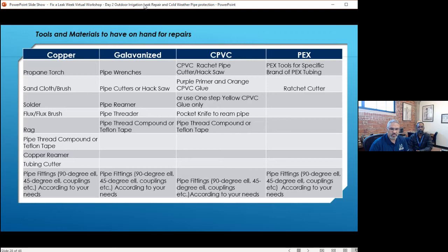You have to use specific tools for PEX installs. You would also use a ratchet cutter. Some PEX piping uses an expander tool that expands a ring to place over the fitting to make the connection and hold it in place. Others have more specific tools for that use. Again, the fittings are insert fittings, barb fittings that go inside the actual tubing.